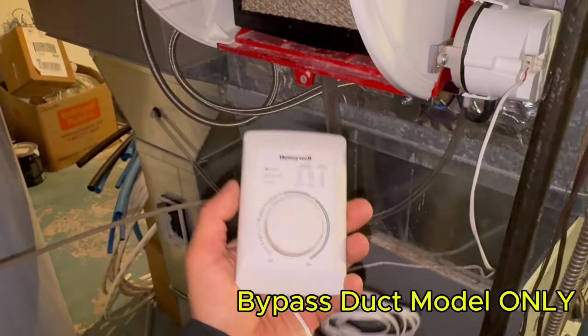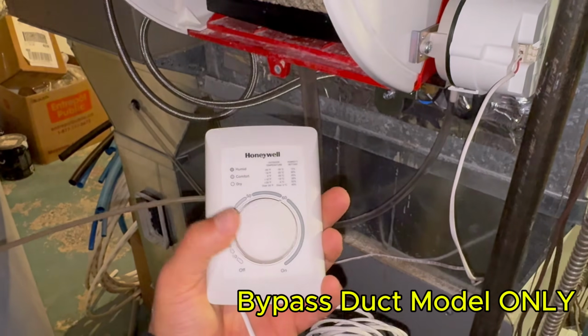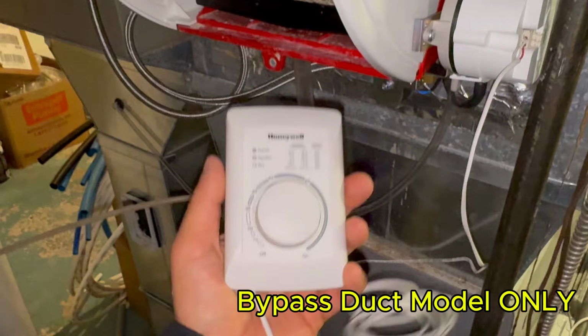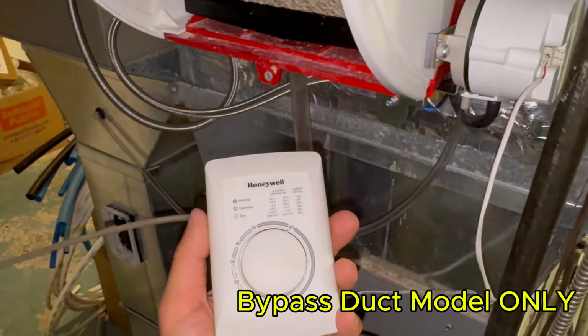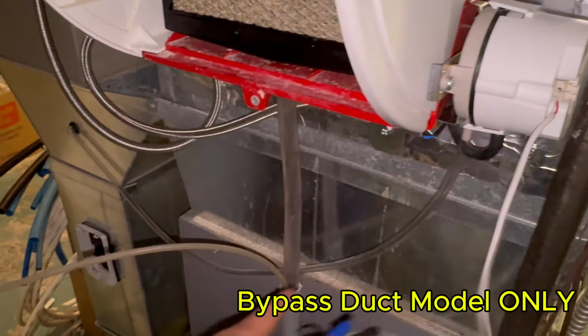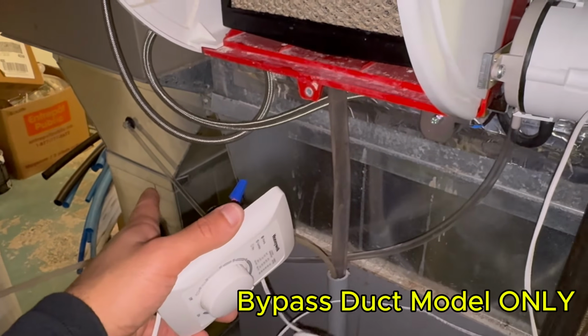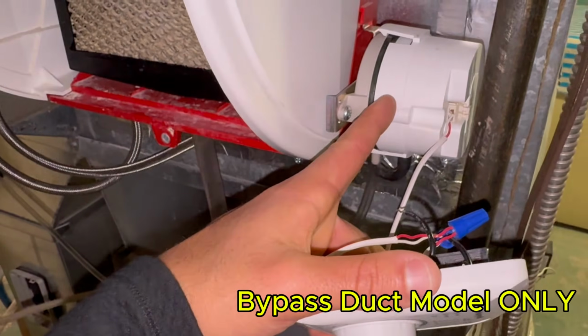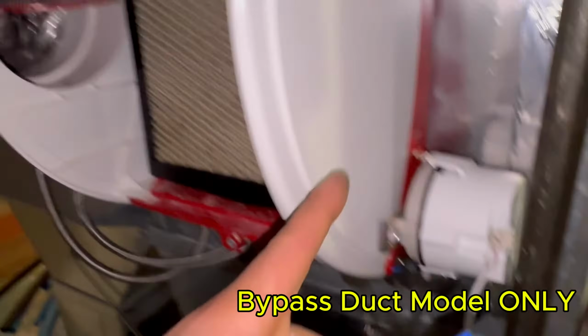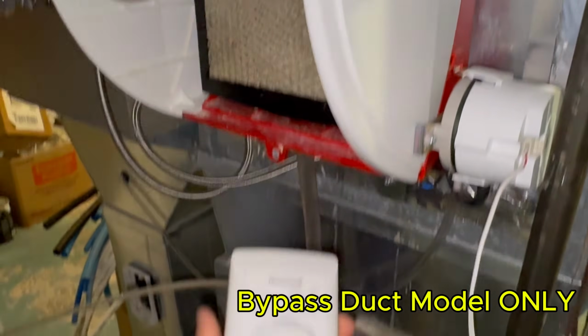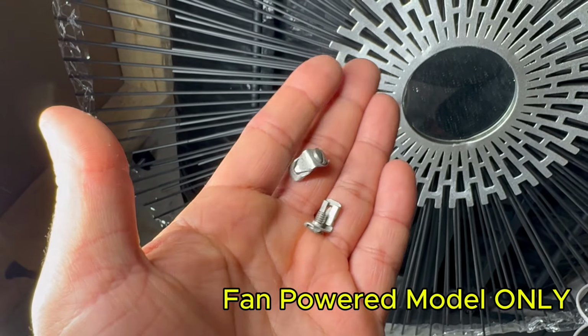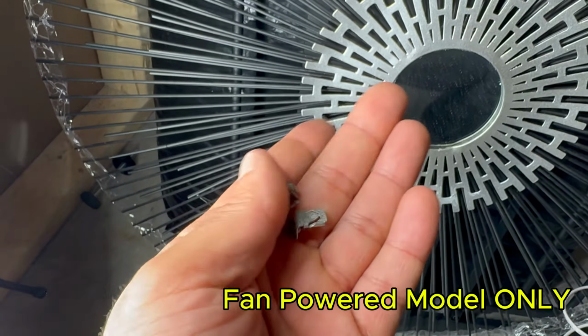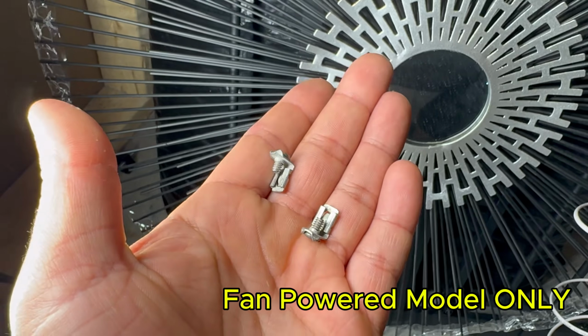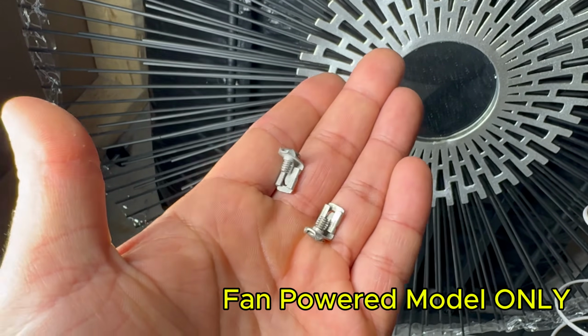And again, the way this works is once you set your humidity, once this asks for additional humidity, it will confirm that there is vacuum on the return side. And if there is, this pressure switch will close, which then will activate your humidifier. The kit comes with these terminals that you're going to connect low voltage wires to, which then connects to the pressure switch. So we're going to do that first.